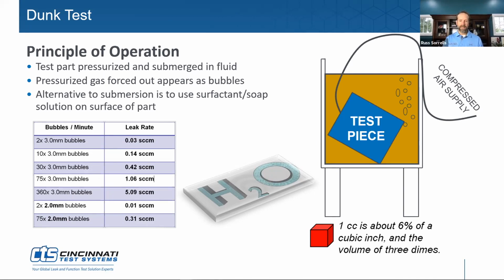We go out onto the floor, and the operator is taking the parts, and she's putting them in the dunk stand. And she hits the button. The dunk stand dunks down, jumps under the water. She turns to a table and dries off the parts, and then moves to packaging, and she packages all the parts. And then by the time she turns around, the dunk stand is raising back up out of the water. And so she takes them and puts the new ones on and sets the other ones off and dries them off and puts them in the dunnage. And the president of our company walks over to her and says, hey, what are you doing here in this station? And she says, oh, this is where I wash the parts. And of course the plant manager had one of those. So dunk testing is very effective as it relates to detecting leak rates, but it's not very repeatable over the long term, is my point. So yeah, absolutely.